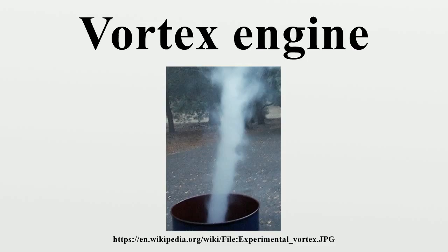Heated air from the crossflow cooling tower enters the concrete vortex arena via two rings of directing louvres and risers. The upper ring of louvres seals the low-pressure end of the vortex with a thick, relatively high-speed air curtain, substantially increasing the pressure difference between the base of the vortex and the outside air, and increasing the efficiency of the power turbines. The lower ring of louvres convey large masses of air almost directly into the low-pressure end of the vortex, and are crucial to achieve high mass flows because air from them spins more slowly, resulting in lower centripetal forces and higher pressure at the vortex.